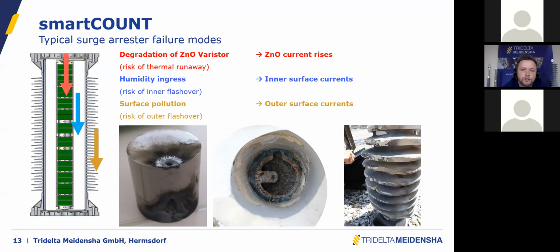Third reason for surge arrestor breakdown, and this is sometimes forgotten, but I will mention it here, is surface pollution. If you have surge arrestors in high pollution areas, you will most probably get a conductive layer on your surge arrestor housing, and then you get outer surface currents, and you run the risk of an outer flashover. So these three cases can appear, and we have three kinds of currents. I have displayed them here with the red, blue, and yellow arrows on this cut view of the surge arrestor. And in the next 3 slides, I will explain how we are capable of measuring those currents and how to distinguish between those 3 cases.